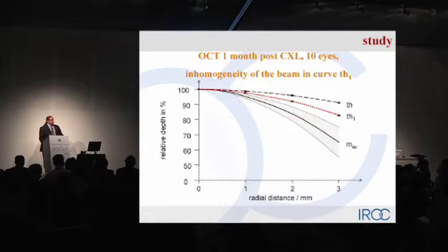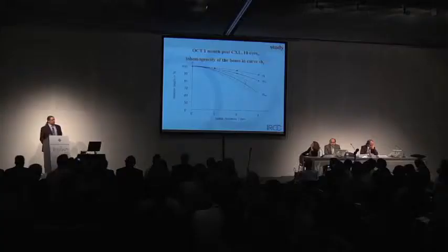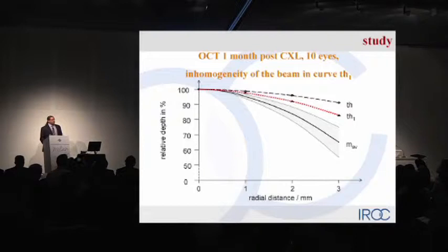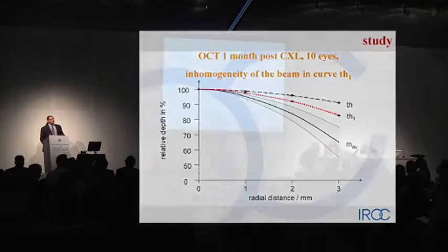Looking at the OCTs of 10 eyes, there's inhomogeneity in the beam and the curvature, and a difference between the amount of cross-linking in the center versus the periphery. If you do some calculations, you identify that we get about 25% less cross-linking in the periphery — that means 25% less light intensity in the periphery — over a radial distance of about 3 millimeters, which corresponds to where Renato Ambrosio found the weakest point. So in order to create a homogeneous cross-linking effect, we have to change from a top-hat profile of constant illumination to doing more cross-linking in the periphery — 3 millimeters away from the center, the light intensity needs to be increased by about 25%.